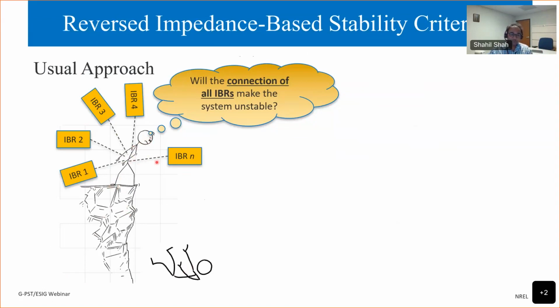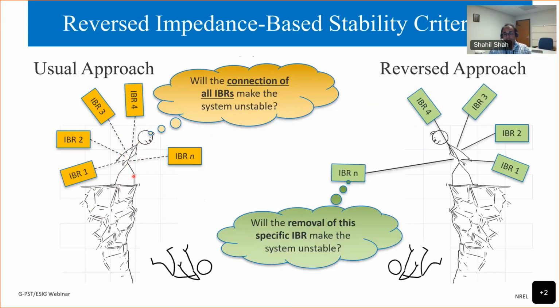So in normal operation, in this approach, we isolate all IBRs, look at the impedance of all IBRs, as well as of this network from those IBRs, and then do the stability analysis. As I mentioned, this is not a scalable approach. So we turn the problem on its head, and we propose a reversed approach. Whenever we are doing the stability analysis, either we see oscillations in the field or oscillations in an EMT study, we start with a stable system. We are never going to analyze a system which is unstable. You can't perform an impedance scan. You can't really do anything when the system is already unstable.